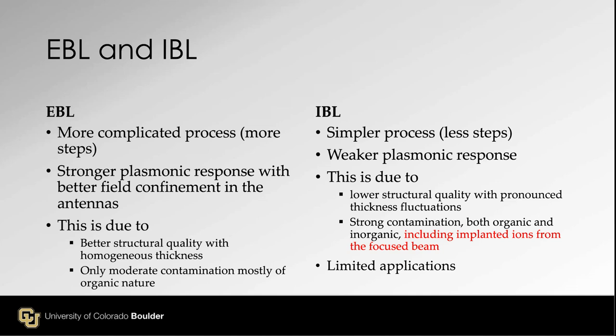So how about different ions? Yes, helium ion microscope. If you use the helium beam, since helium is a gas, there's less implantation issue, though there are still some issues with helium implantation. Xenon is also a noble gas, so it has less contamination issue. However, xenon plasma can also change surface properties - not so much contamination, but it can damage the crystal structure. So there are good things and bad things for both cases, but when you want to make devices, you have to think about which method you want to use.